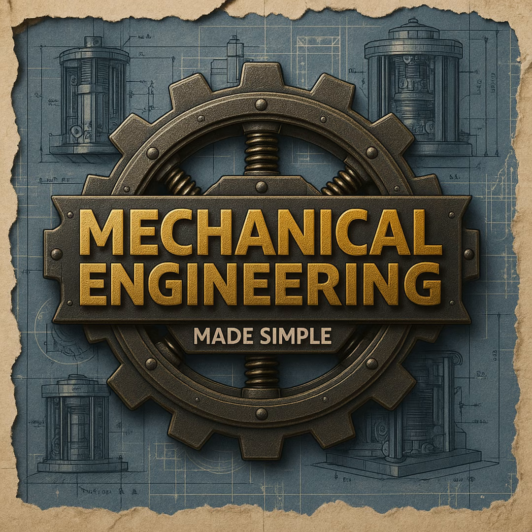Exactly. To achieve that in a massive industrial condenser, you would have to constantly coat the metal with special promoters or polymers or noble metals. Okay. And in a real-world, high-temperature, high-pressure environment, those chemical coatings degrade incredibly fast. Oh, so it just wears off. Yeah. It is simply not economically or physically viable to maintain that perfect waxed car finish for decades. So film condensation basically becomes the default reality that engineers simply have to deal with. We play the hand we're dealt, basically.